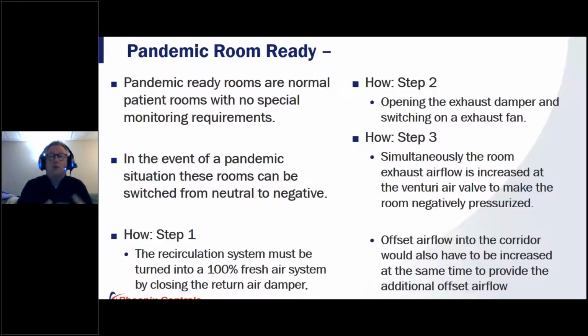Step 2 is basically to open the exhaust damper and switch on the exhaust fan, right? So now you have a dedicated exhaust fan for that pandemic ready situation. You basically turn that on, and at the same time, you increase the exhaust airflow. So again, for the Phoenix valve, we go to a higher position, usually increasing the airflow on the exhaust side by around 15%, and that way we make sure that we're exhausting more air than what we're bringing in on the supply side, creating that negative direction, right?